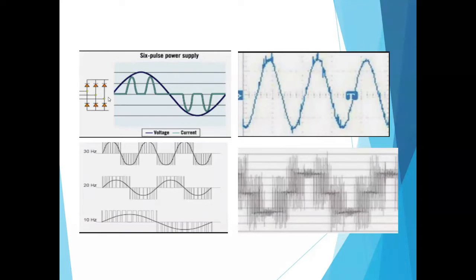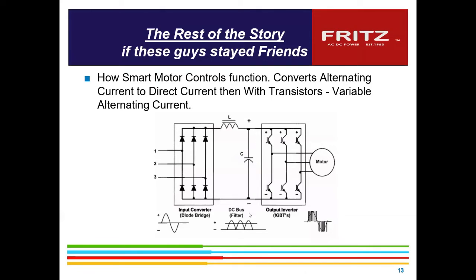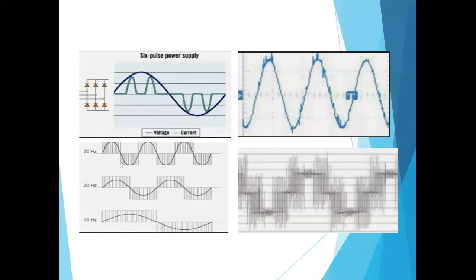So as you can see here, this is the power coming into that grid, and you can see the actual current flow going into the diodes feeds in pulses, because they're recharging and filtering this DC bus power so that it stays, on a 480 volt machine, at about 760 volts DC. Then they take that and refire it out. This is what the input pulse looks like, and you have to be aware of it when you have multiples of these machines together, because you get a lot of pulsing and some jagged waveforms, and that's what they call harmonics. So there are things you want to check when installing drive controls, to make sure they're set up correctly in the circuit.